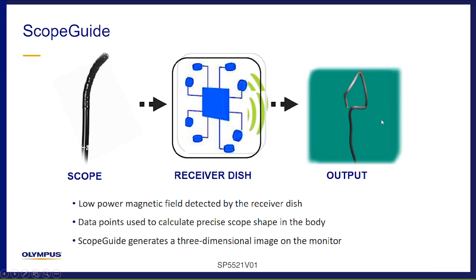A hand coil, and you'll see this in some upcoming slides, the hand coil allows your nurse or technician assisting you to apply direct pressure onto the patient's abdomen where you see your loops on ScopeGuide. So instead of marching around the abdomen, when you're looping and you're getting paradoxical movement and you're trying to reduce your loops, you know how it goes now. Your nurse tries the left lower quadrant. She may try the left upper quadrant. She tries that sequential push until you get the right spot. Well, using the hand coil, you can apply direct pressure exactly to where you need it, which would save time and be much more efficient in your procedure.